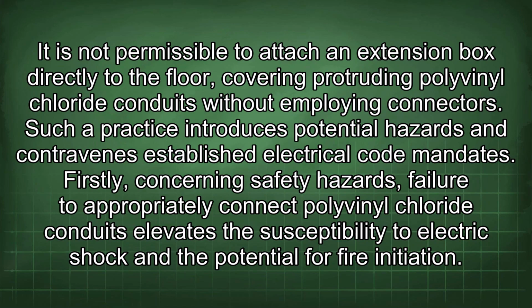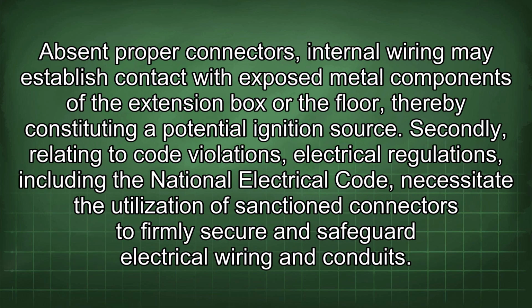It is not permissible to attach an extension box directly to the floor, covering protruding polyvinyl chloride conduits without employing connectors. Such a practice introduces potential hazards and contravenes established electrical code mandates. Firstly, concerning safety hazards, failure to appropriately connect polyvinyl chloride conduits elevates the susceptibility to electric shock and the potential for fire initiation. Absent proper connectors, internal wiring may establish contact with exposed metal components of the extension box or the floor, thereby constituting a potential ignition source.